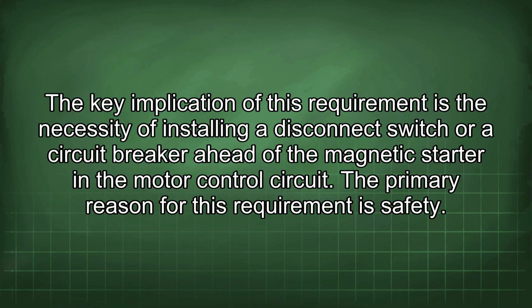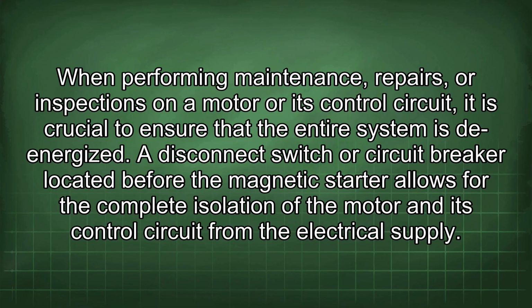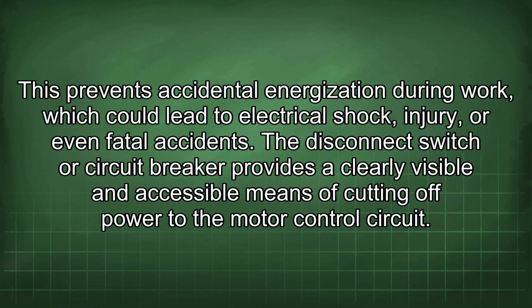The primary reason for this requirement is safety. When performing maintenance, repairs, or inspections on a motor or its control circuit, it is crucial to ensure that the entire system is de-energized. A disconnect switch or circuit breaker located before the magnetic starter allows for the complete isolation of the motor and its control circuit from the electrical supply. This prevents accidental energization during work, which could lead to electrical shock, injury, or even fatal accidents.